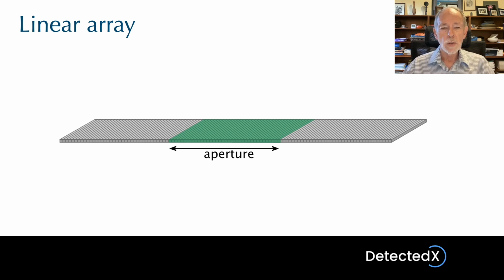The next idea I'd like to introduce is that only a group of elements is used at any one time to transmit and receive ultrasound. And I've highlighted that in green. So a block of elements, a group of elements, is selected electronically, and only those elements will be used to transmit and receive at one particular time. So the rest of the transducer is not active at that particular time, only that region. So obviously that defines the aperture that the machine will be using, and therefore it defines parameters such as the beam shape.